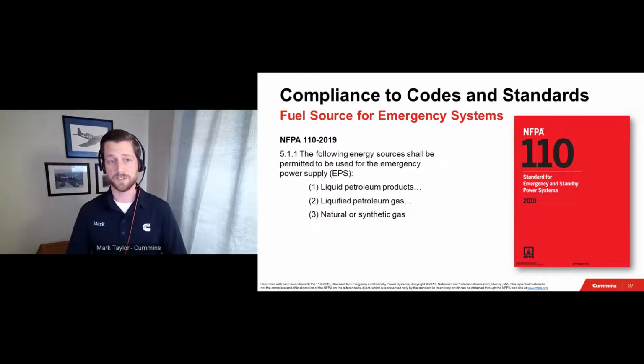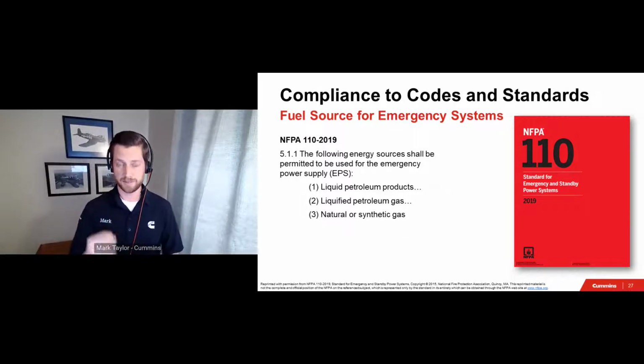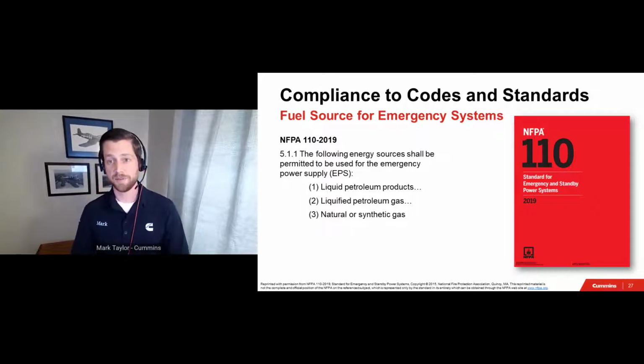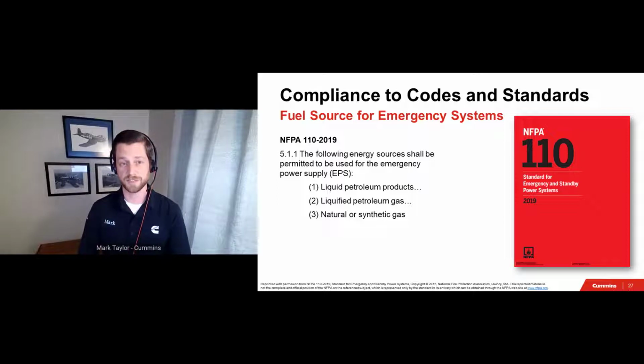One of the leading concerns for gaseous fuel generator sets centers around the applicability of such a fuel for emergency standby systems. In the eyes of NFPA 110, and this is a snippet from the 2019 version, the emergency power supply, that's the generator set itself, can be permitted to be fueled by liquid fuel, liquefied petroleum gas, which is commonly seen as propane, or of course, natural or synthetic gas. So just to be clear, a gaseous fuel generator set is okay in the eyes of NFPA 110 in this section. NFPA 110 also contains requirements pertaining to on-site storage of said fuel sources, and I'll be spending the next handful of slides on this point.